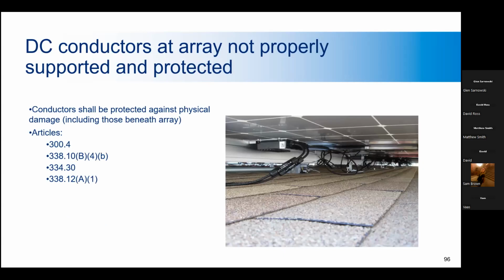One of the most common installation errors on a rooftop is where the conductors are not properly supported and are just laying on the roof, and they're subject to damage by wind, snow, ice, movement from wind, and especially they rub against the abrasive shingles they're in contact with, and that can cause the wires to fail. Another potential hazard in this kind of situation is squirrels or animals nesting underneath the panels. They like to chew on the wires. What you can do about that is install critter guards, which are basically metal or plastic mesh that surrounds the array and blocks the critters from getting between the array and the roof. Another thing to keep in mind is the wires can also catch debris, which can cause drainage issues and then cause problems with the roof.